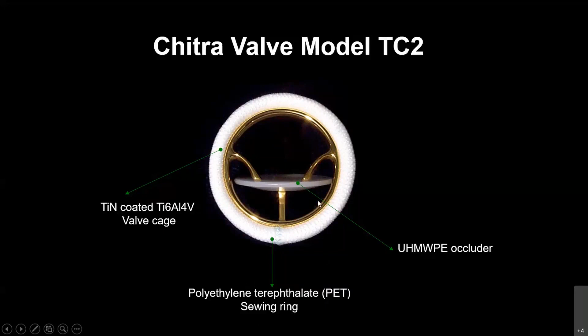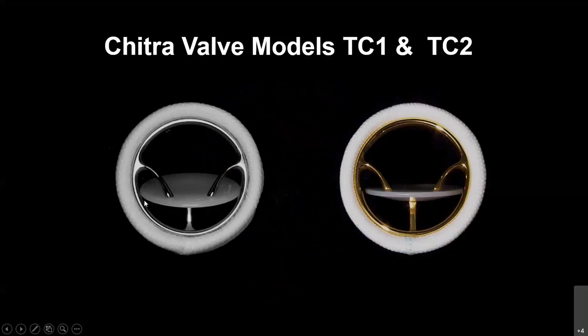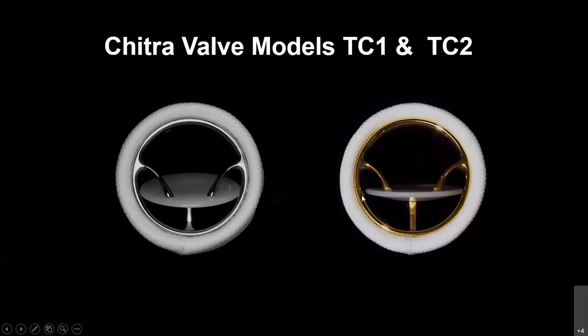Here, the basic difference between this and the previous model is what we call the minor orifice flow area. That is the area available for flow in the open condition in the minor orifice. This has been enhanced from 26% of the total to 33% of the total. That's about a 30% increase in the minor orifice flow, thereby reducing the thromboembolic events in the minor orifice region. Once the flow is better, any microthrombi which get formed will get washed off and it won't allow the thrombi to build there.